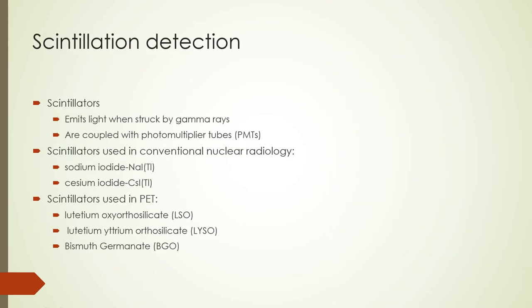The next type of detector we shall learn about is the scintillator. A scintillator is a material that emits visible light when struck by x-rays. The light intensity is very low and must be amplified and converted to an electrical signal before it can be used. In nuclear medicine devices, this is done using a photomultiplier tube. A scintillation detector is basically a scintillator coupled to an amplifier like a photomultiplier tube. The scintillator commonly used in nuclear medicine is sodium iodide crystal doped with thallium. Cesium iodide doped with thallium can also be used. Other scintillators like lutetium oxyorthosilicate (LSO), lutetium yttrium orthosilicate (LYSO), and bismuth germanate (BGO) are used in PET applications.